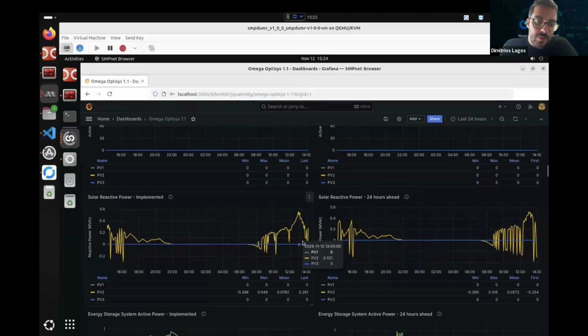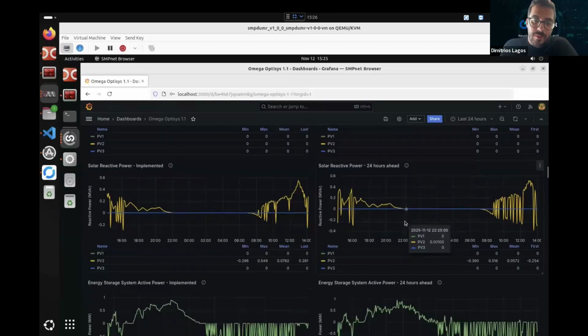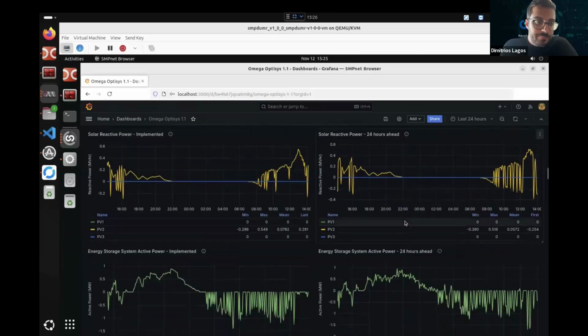I should also add here that Optisys is adaptive, so it is executed every 5 or 15 minutes, depending on the user preferences. These profiles are updated every 5, 15 or 30 minutes based on the latest forecast and the latest measurements from the grid, which also give the active topology of the grid. So even if there is a 24-hour horizon in the graphs that we see on the right, these are constantly updated. They always take the latest status of the system into account.